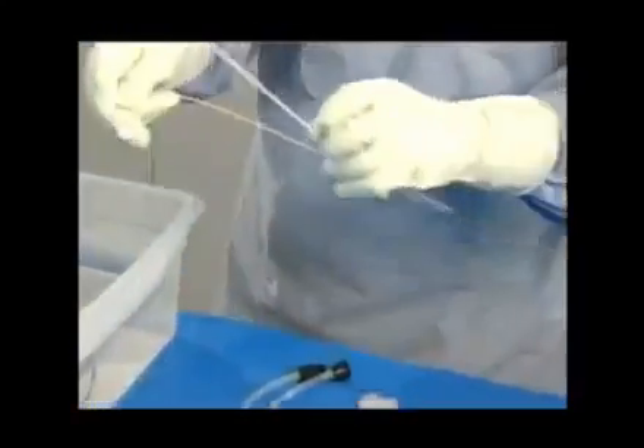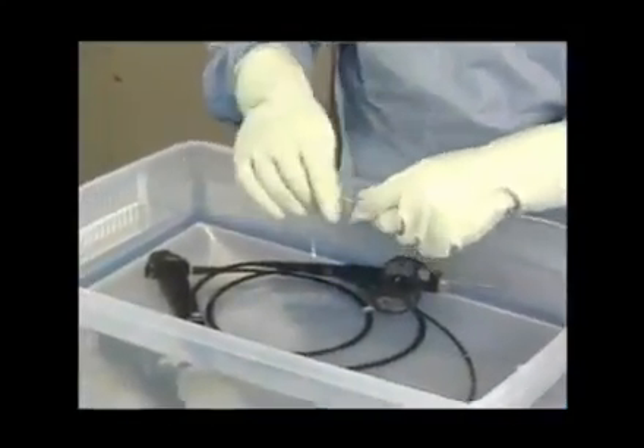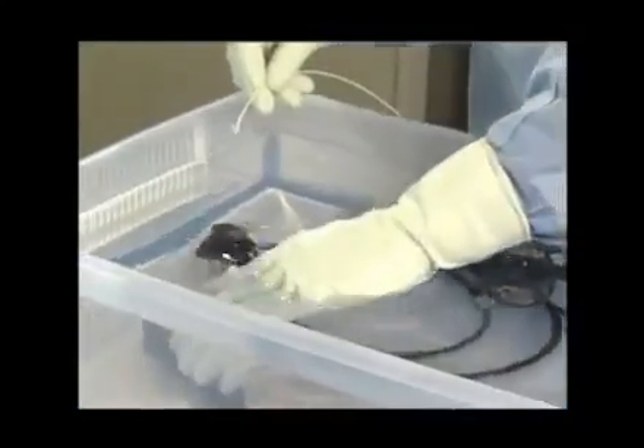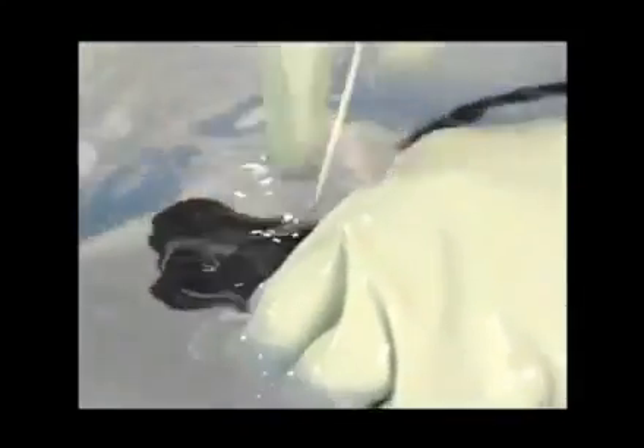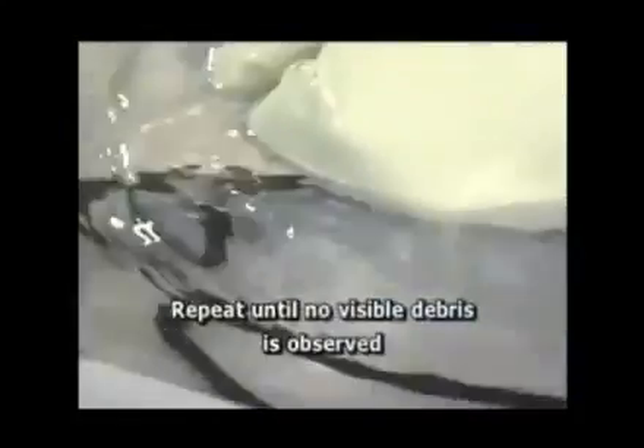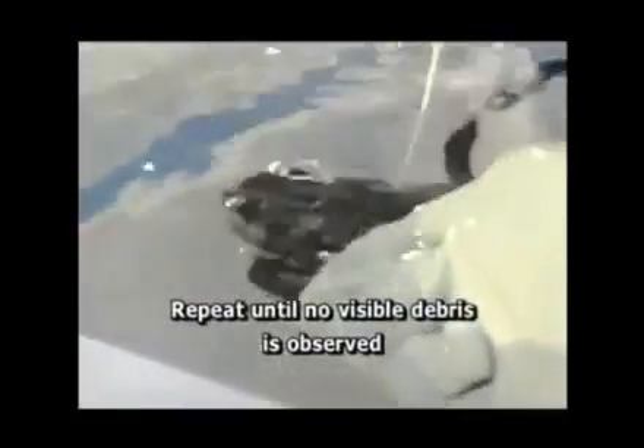Next, brush the channels. Start by inspecting the channel cleaning brush for any damage. To clean the suction channel, insert the brush into the suction valve cylinder. Use short strokes to advance the brush through the insertion tube until it emerges from the distal tip. Remove any debris from the bristles with your fingers and gently pull the brush back through the channel. Inspect and clean the bristles again. Repeat this process until you cannot see any further debris on the bristles.